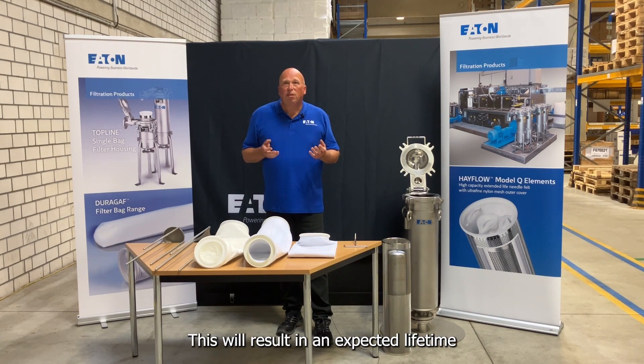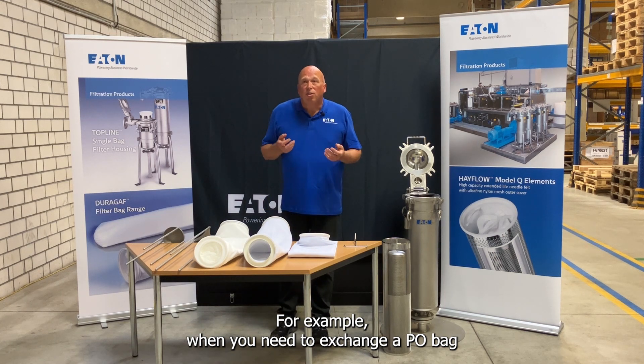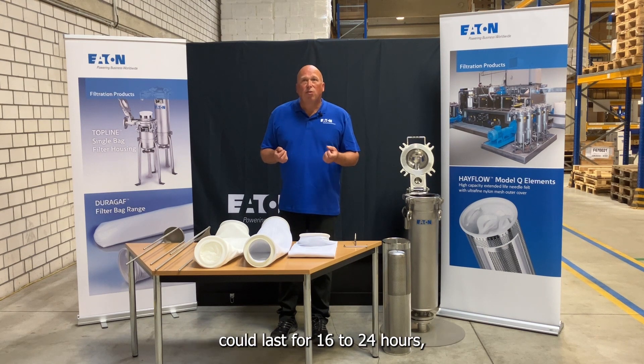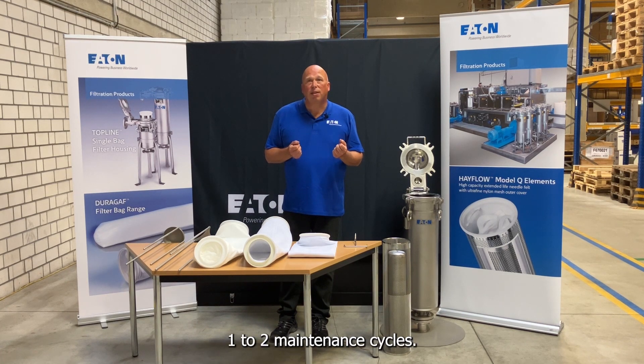This will result in an expected lifetime of the same factor. For example, when you need to exchange a PO bag every eight hours, a corresponding POXL bag could last for 16 to 24 hours, diminishing or eliminating one to two maintenance cycles.